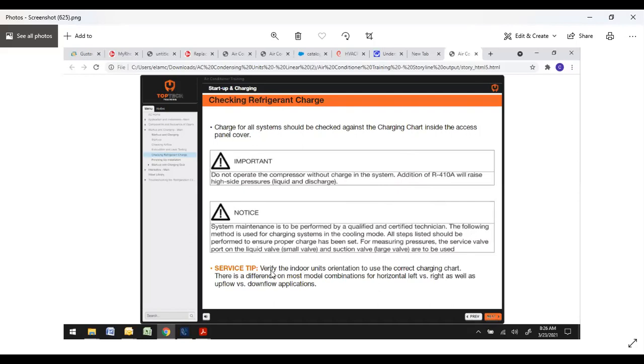Service tip, this is huge. Not as imperative on air conditioners, but on heat pumps, it can make the difference whether you're right or way wrong. Verify the indoor unit orientation. So you make sure you use the correct charging chart, which we'll go over here in a minute. There can be a difference. It just depends. Unit to unit's all different. It's not as severe on air conditioning only. There can be a difference between upflow, downflow, horizontal left, or horizontal right. So if you don't know what you're looking at, and you look at the wrong chart, you could literally be way off. Like I said, it's not so severe in cooling, but in heating it is.